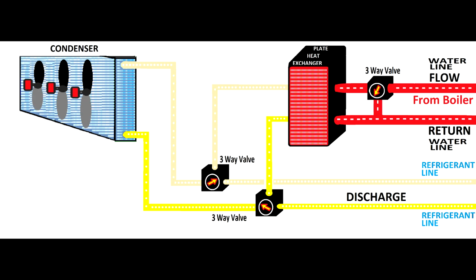If the system is short of refrigerant and the plate heat exchanger is also not a very good design, then the boiler will try to compensate, and you will push heat into this plate heat exchanger, and the bypass will be active as well. And you can see both pipes are red, because the plate heat exchanger will barely have the capability to boost the water temperature, so the boiler will do most of the job.